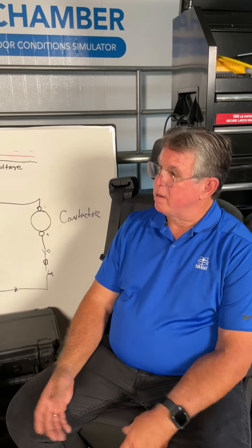Yeah, another thing, we've been doing a lot of apartment complexes, working with some contractors, and one of the things we're running into are a lot of broken wires and bad thermostat subbases. In diagnostics, I kind of like to divide and conquer. So I'll go to the air handler and jump the R to the wire going out to the condensing unit. I'm not going to say yellow because unfortunately half the time it's a red and white wire or a black and a red wire. So you have two wires going out there. Yep. But if I jump from red to the non-common wire going out to the condensing unit, and the condensing unit comes on, that tells me that from that point out is good.